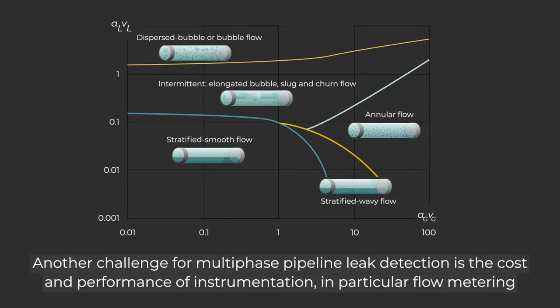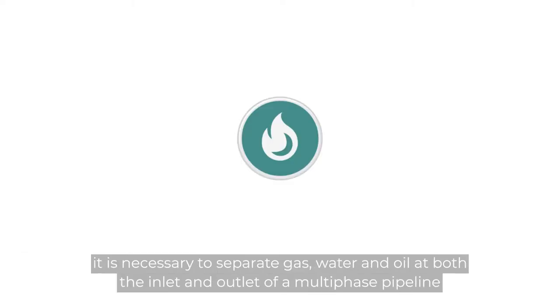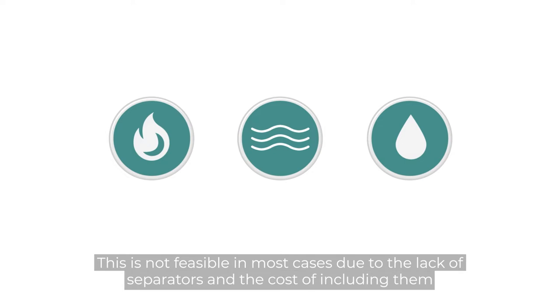Another challenge for multi-phase pipeline leak detection is the cost and performance of instrumentation, in particular flow metering. To achieve a similar level of accuracy as a gas or liquid pipeline, it is necessary to separate gas, water, and oil at both ends. This is not feasible in most cases due to the lack of separators and the cost of including them.